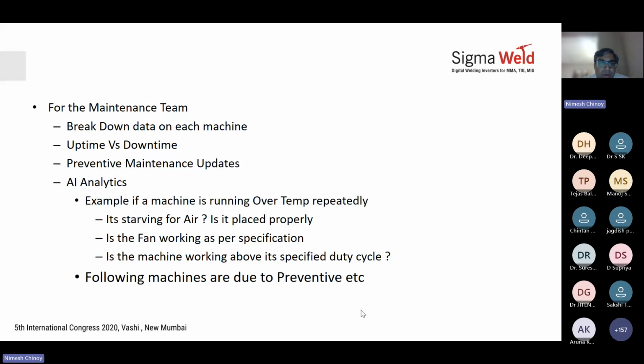AI analytics on the data collected - for example, if a machine was running over temperature repeatedly, what can be the reasons? Is it starving for air? Is it placed properly, meaning is the airflow correct or not? Is the fan working as per specification? Or is the machine working above its specified duty cycle? One of these three can be the reasons.